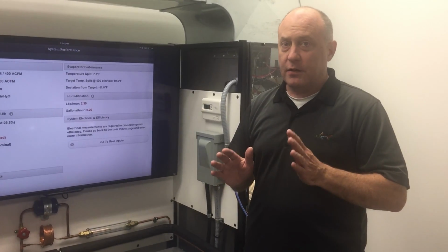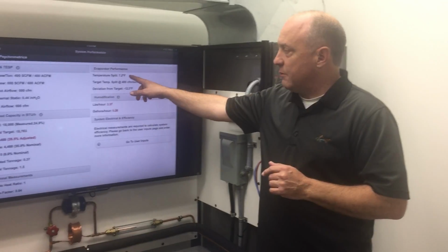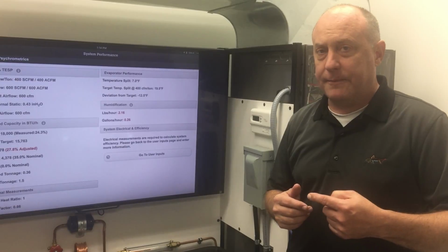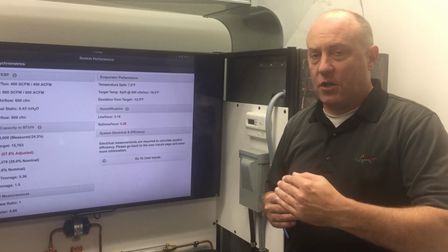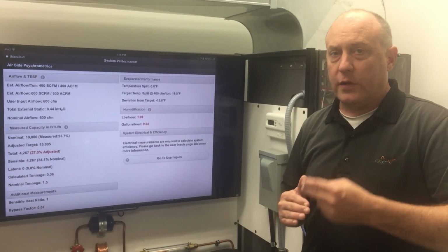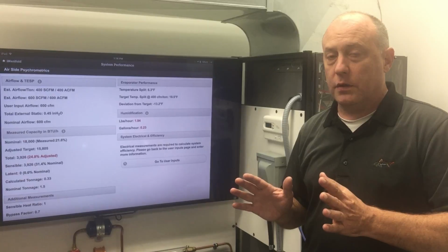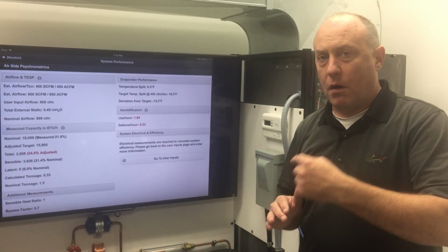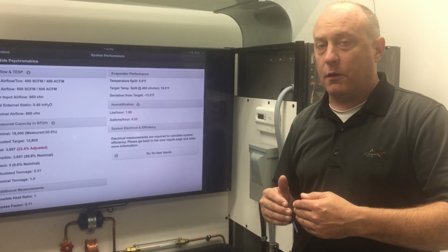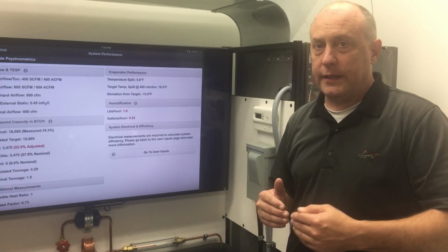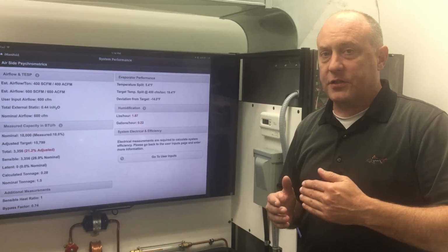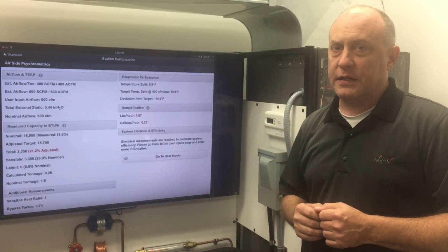And the other thing that's happening here is really cool if you stop and think about it. Because we have this sensible cooling going on, it's also keeping the system from running again. In other words, when the thermostat shuts off and it's just controlled by temperature, if we get free cooling and we continue to cool that air down by making our system an evaporative cooler, we're going to prolong the thermostat calling for cooling again, which means that we're not going to dehumidify. So not only are we rehumidifying with sensible cooling, but we're prolonging the point to where we're going to dehumidify again. And all that water that's on that coil re-evaporated into your house, so not a good idea.